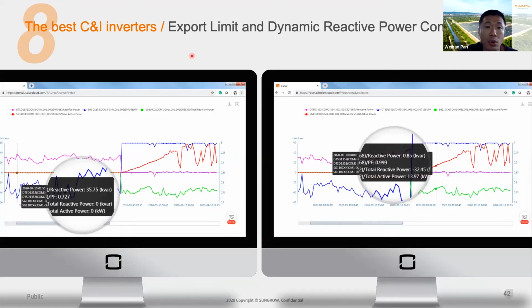But why do you need dynamic reactive power control? For example, you can see from the screen here, without reactive power control, the power factor sometimes might be less than 1, in this case 0.7, which means you might sacrifice more active power to do the reactive power compensation. With the dynamic reactive power control, we can keep the power factor at almost 1, which means we will have less power loss and gain more energy output.